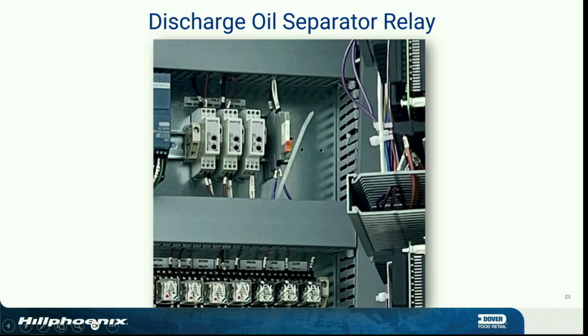Any alarms are going to come out of your digital inputs. We do alarm if your separator's high for 25 minutes. We're going to alarm, let you know something's wrong. Because if you don't transfer oil with a 300 to 600 pound differential in a couple seconds, something's wrong. All right? You don't need to change that flex count. That flex count works everywhere. If you extend it, you're putting a Band-Aid on the problem. That's all you're doing. Okay?